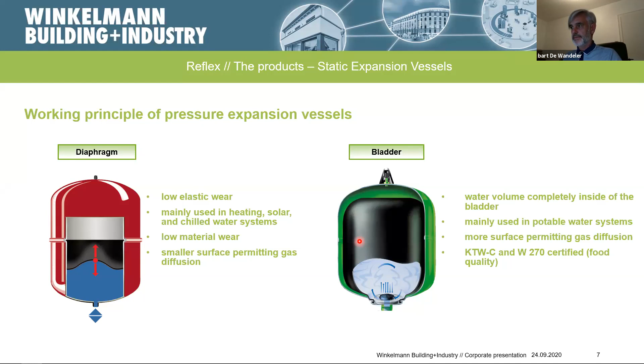But of course, both can be used for heating as well as for cooling. The big advantage that we also have with bigger bladder vessels, when you have a vessel, for example, of 2,000, 3,000, 10,000 liter, is that if there is a problem with the bladder, an installer is always able, also with smaller vessels, of course, to replace a bladder, and then you can restart the working principle of the expansion tank.